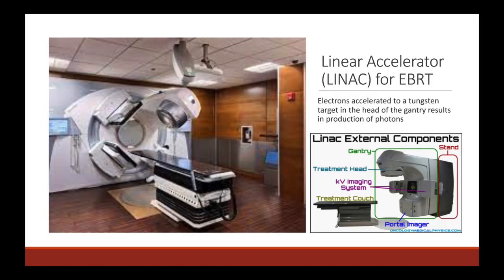External beam radiation is delivered using a machine called a linear accelerator, abbreviated LINAC. A linear accelerator accelerates electrons to a tungsten target, resulting in the production of photons in what is known as the head of the gantry. The head of the gantry is then angled around the patient in various ways, and these photon treatments are delivered. The photons — also known as x-rays — come into the patient's body from different angles, delivering low doses throughout the body, but the area where they all overlap is usually the target area.